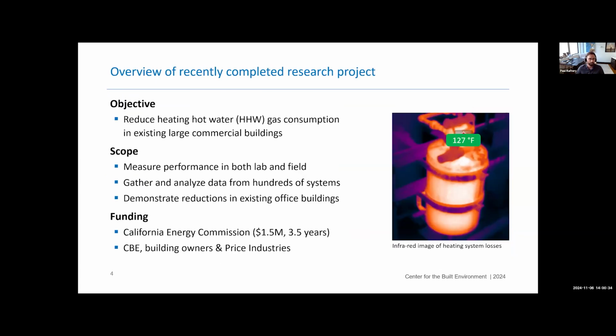So the project that I'm going to be talking about today was just wrapped up this summer, actually, and it was funded by the California Energy Commission. And its focus was really on identifying ways to address existing large buildings and reduce the amount of natural gas that they consume in an effort to cut emissions and cut costs. And we really focused in on the heating hot water systems in these buildings. So the hydronic heating systems, so the hot water that's used to heat the building more than heat the domestic hot water that's coming out of faucets or showers or whatever in the building.